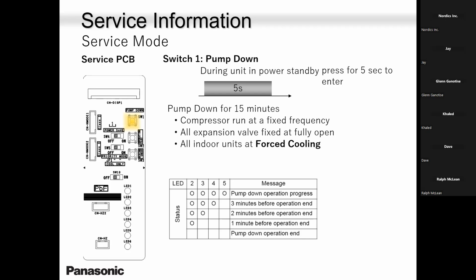Let's say you go to the homeowner's house and you need to move the outdoor unit for whatever reason. You can move it without those guys being there. Just push the unit into test run cooling and you're good, or pump down. You can do the pump down process before the homeowner comes, or even if they don't want to come, that's fine. Pump it down, collect all the refrigerant into the outdoor unit, close it, move the unit, reinstall it, re-vacuum, pressure test, you name it, and you are up and running again.